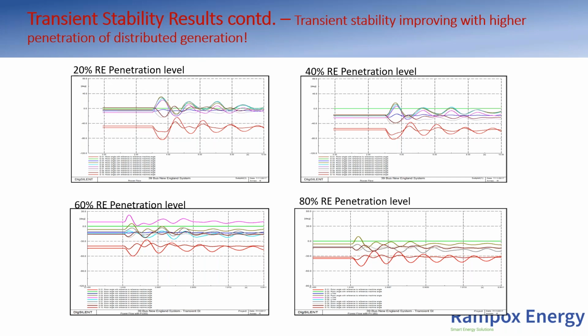What happens is that when you have generation close to the load centers, those generators at the far end, your normal synchronous generators, now pull back. They don't have to provide power the way they used to before. So their governors pull back. When their governors pull back, their operating angles pull back. When the operating angles pull back in terms of that torque angle, there is an improvement of stability.